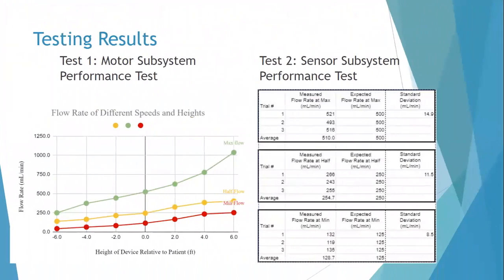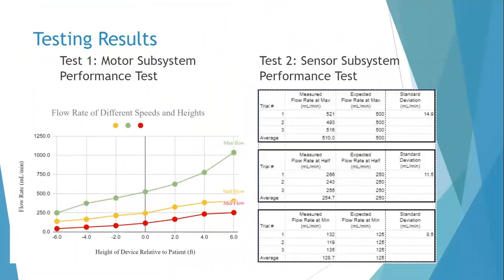Given our testing conditions for the motor subsystem, we were able to validate the device's functionality, guaranteeing it operated within its optimal range of 250 milliliters per minute at any orientation between the device and the patient. Additionally, the sensor subsystem test validated that it fell within a 5% standard deviation range of the desired flow rate compared to the lab-grade sensor, guaranteeing accurate fluid administration.